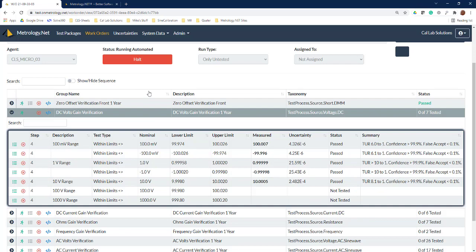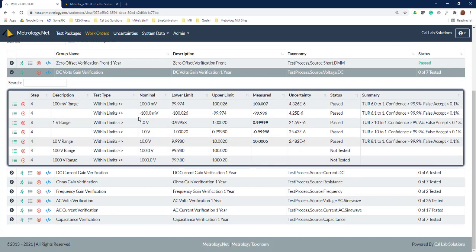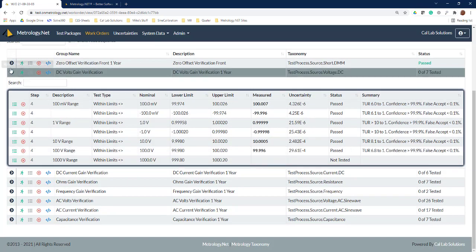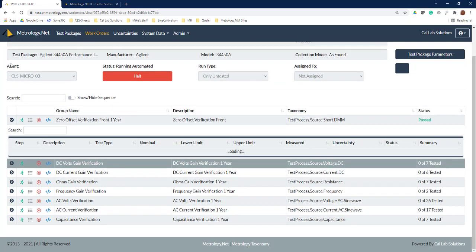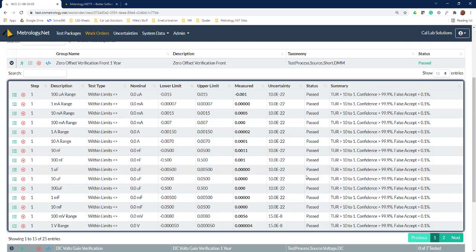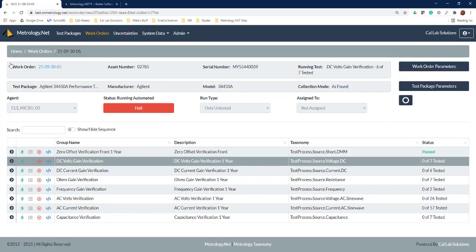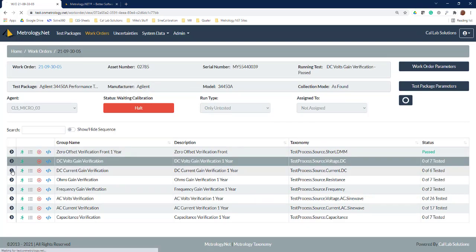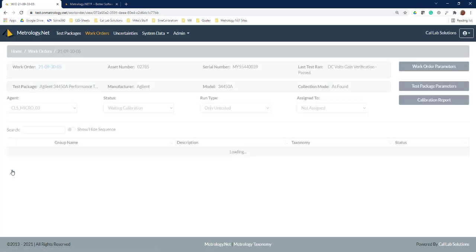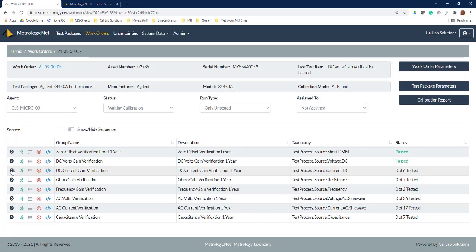Some additional features: we can go ahead and hit the halt button if we want to stop this calibration. It'll stop the calibration on the data that we're working on and move on to the next data point. We also have the ability in the UI that we can come in here and start looking at any other data points that we want to come in and look at. So the UI allows us to come in and look at the parts that we want to look at.